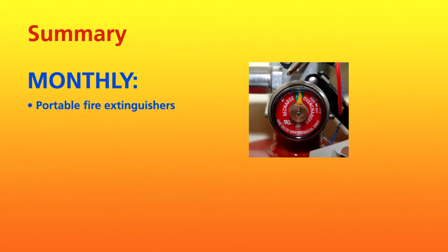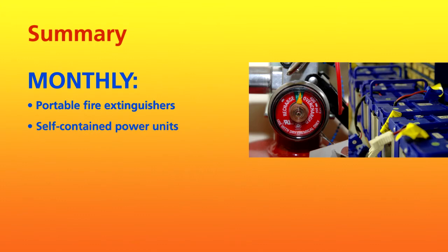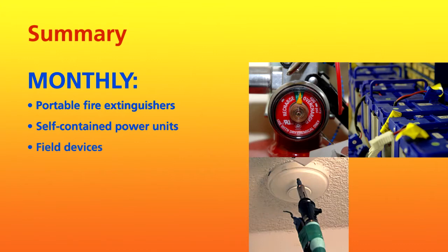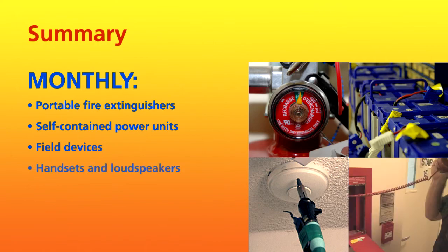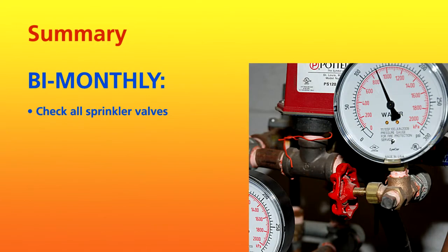On a monthly basis, the following elements must be inspected and recorded in the building's fire log book. Portable fire extinguishers for obstructed nozzles, tamper seal, and pressure gauge. Self-contained power units including battery, terminal connections, and clamps. Field devices such as heat detectors or pull stations inspected on a rotational basis, and firefighters' handsets or loudspeakers. Check all sprinkler control valves every 2 months.